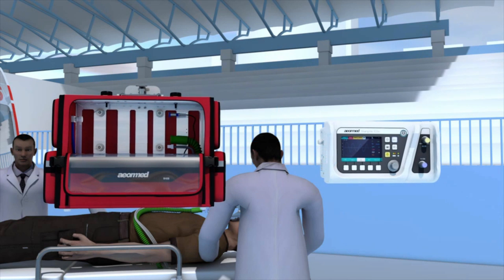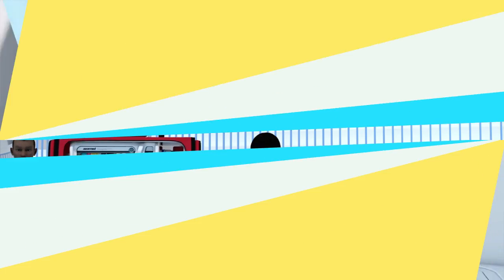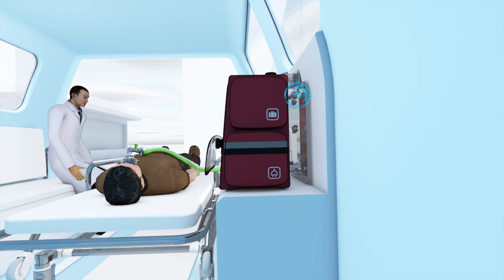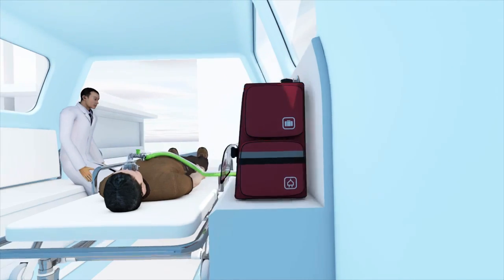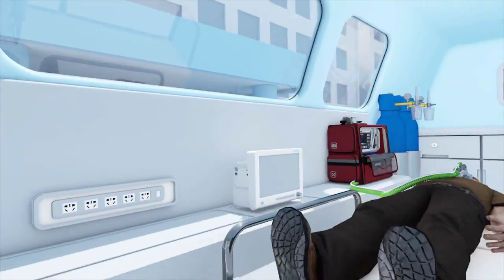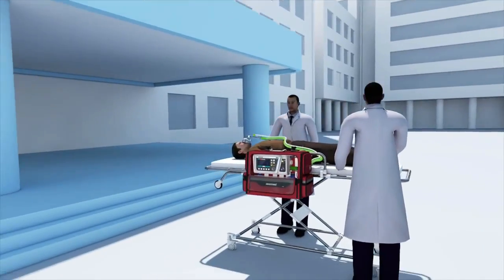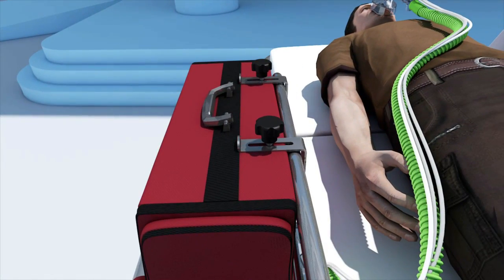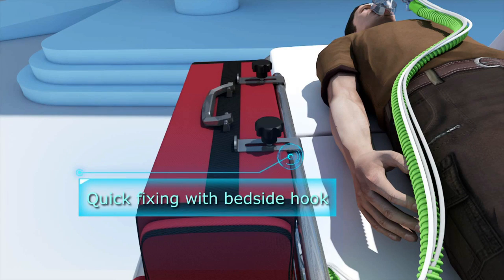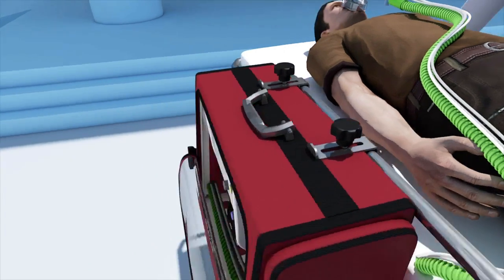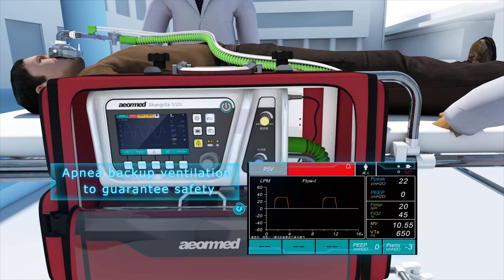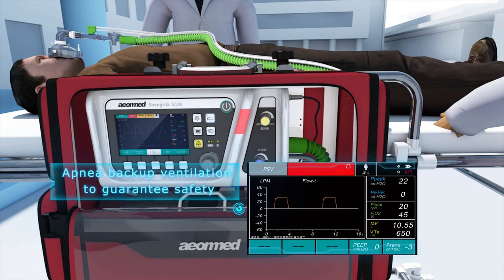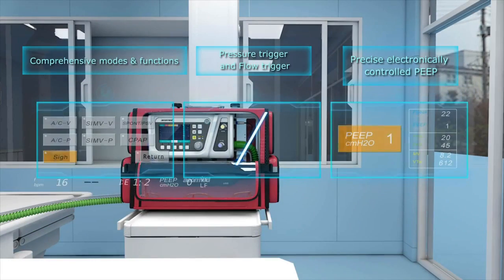These units typically consist of a flexible breathing circuit, a control system, monitors, and alarms. Power is typically supplied by one or more internal batteries, an external battery, or an alternating current line. Common operating modes available on these units include control mode, assist control mode, and SIMV mode. Some may have additional operating modes such as CPAP and pressure support to facilitate patients with more complex oxygenation and ventilation requirements.